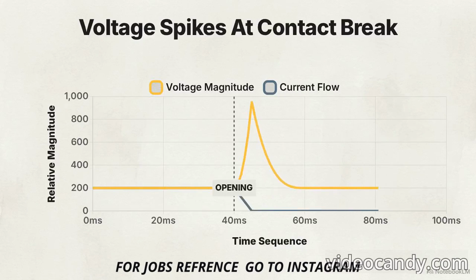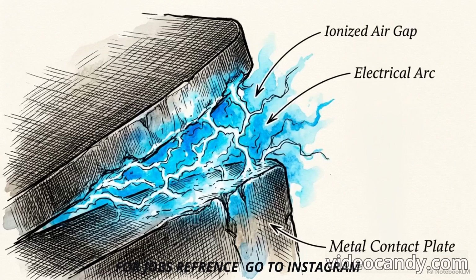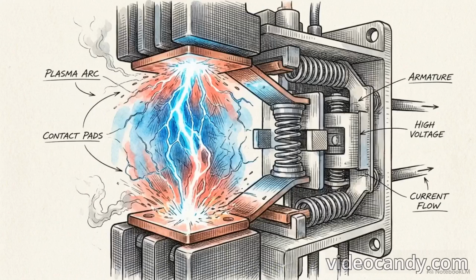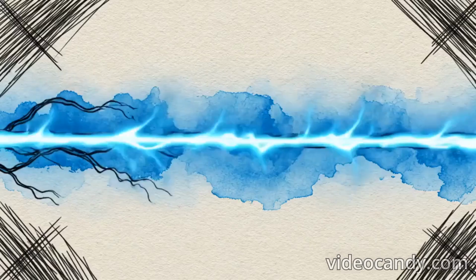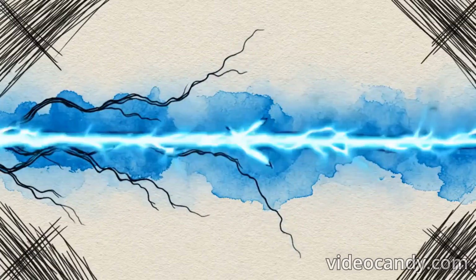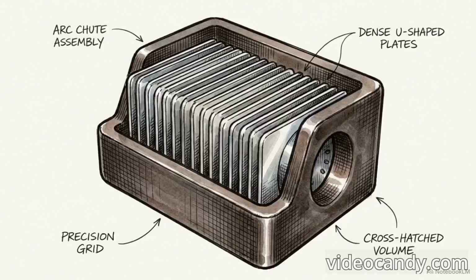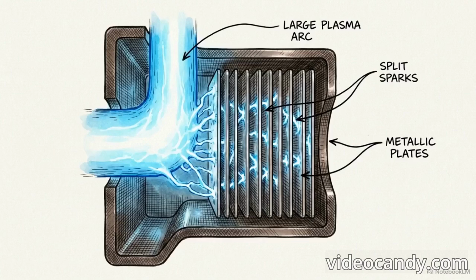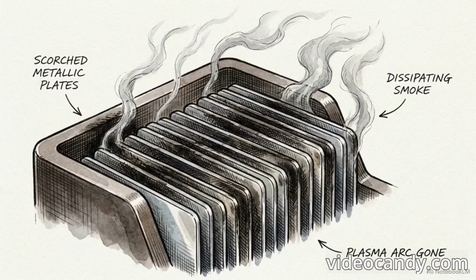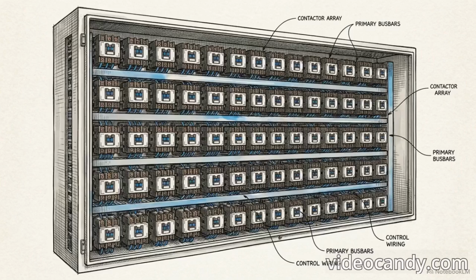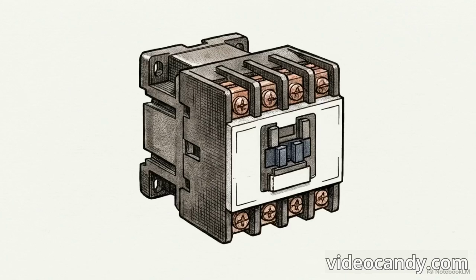But the most destructive forces emerge during the opening sequence, visible here as a sudden exponential voltage spike. As mechanical contacts separate, the motor's inductive load violently resists the current drop, driving the voltage exponentially higher, a phenomenon known as inductive kickback. This extreme voltage spike strips electrons from the surrounding air molecules. The air itself ionizes, creating a highly conductive plasma arc that continues to bridge the physical gap between the separating contacts. To break the circuit completely, this violent plasma arc must be immediately stretched, split, and rapidly cooled into darkness. The contactor achieves this mechanically using internal arc chutes. These metal plates draw the arc outward, physically elongating it and splitting it into smaller, cooler segments, until the electrical resistance is too high for the plasma to survive.